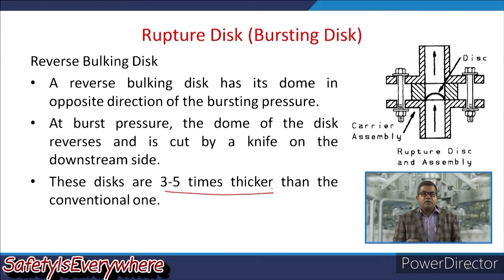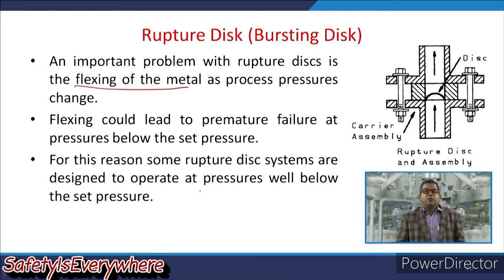Now an important problem with the rupture disc is the flexing of metal as process pressure changes. So if the process pressure is fluctuating, then there may be a problem of flexing of the metal. Flexing could lead to premature failure at pressures below the set pressure. So this you may term as the disadvantage. For this reason, some rupture disc systems are designed to operate at pressure well below the set pressure. So this is the crucial aspect.